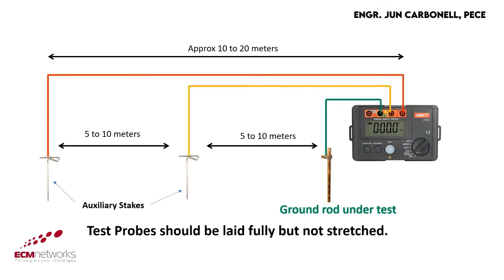The yellow test lead should be clipped to the auxiliary stake located at the middle point between the farthest stake and the ground rod, at least 5 to 10 meters. The green test lead should be clipped on the tested ground rod.